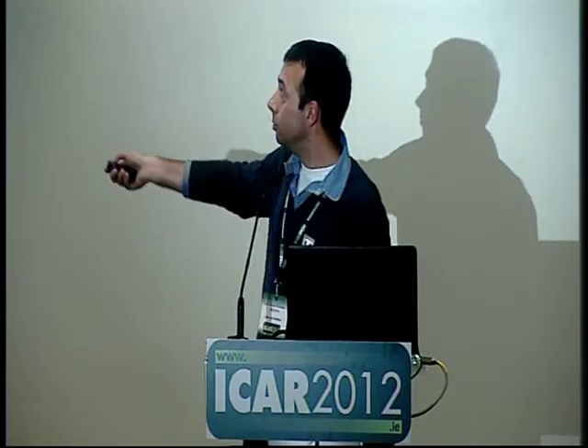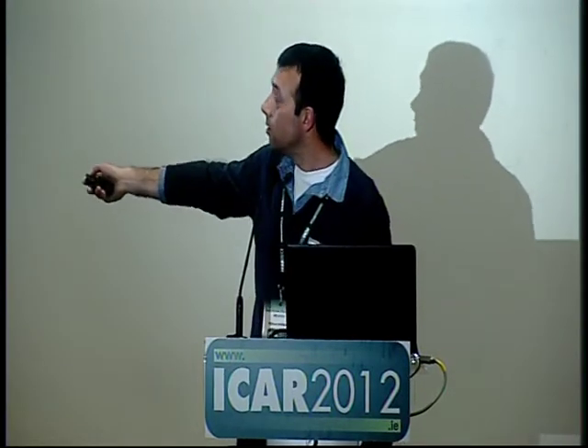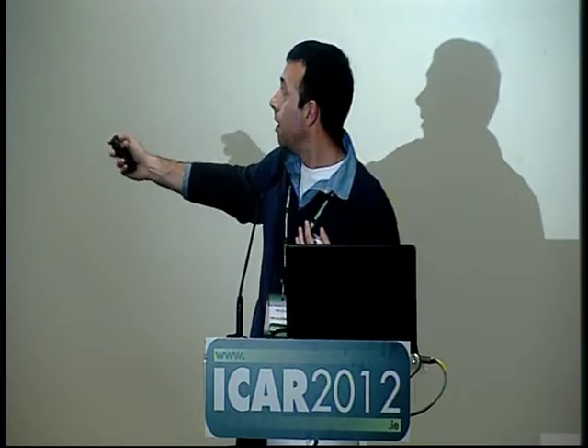So here, again, in another funny way to do it, you do this wavelength by wavelength. You determine all these B coefficients, all the offset values, and then when you have a new sample, an unknown spectrum that you want to standardize, you just apply the different coefficients that you have obtained. And this is done for every slave of the project, okay?